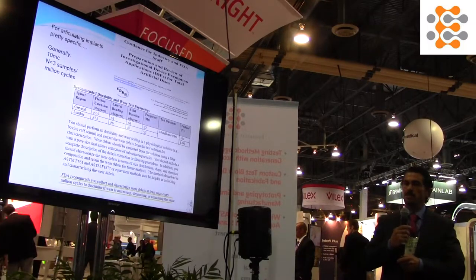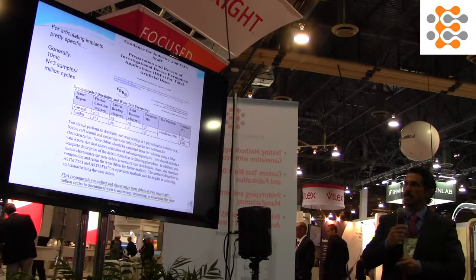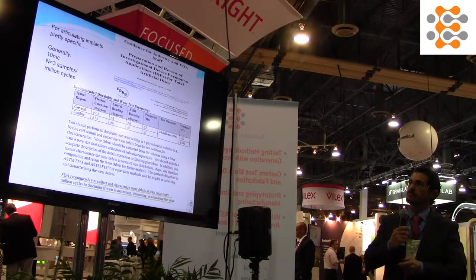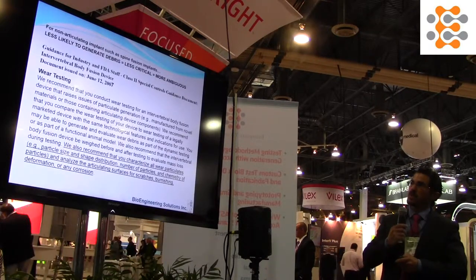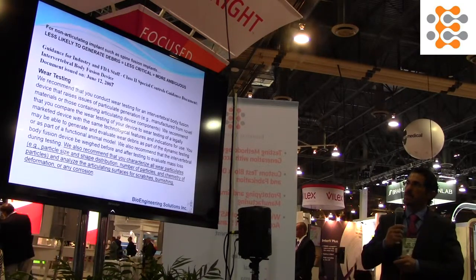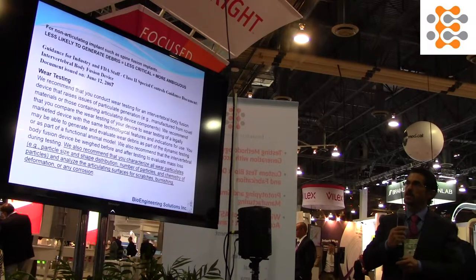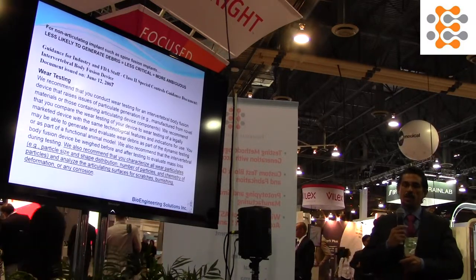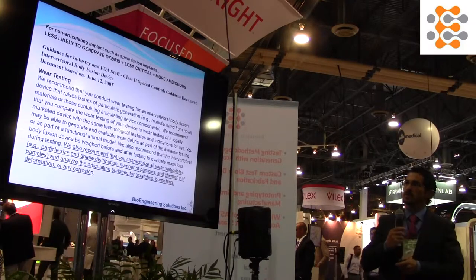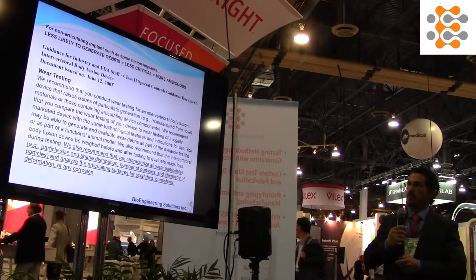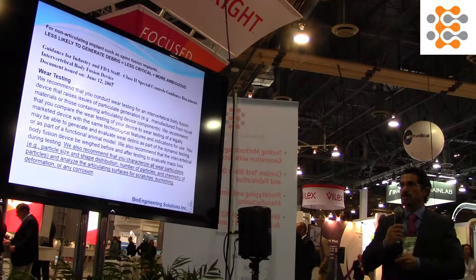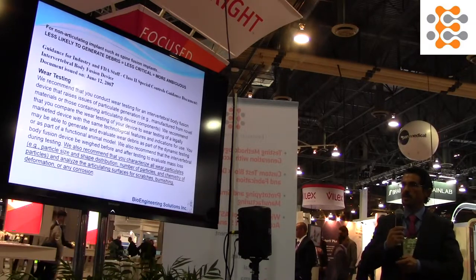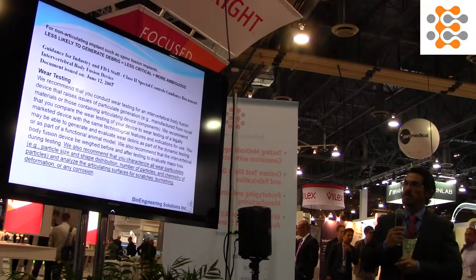If they stay the same, it's enough to convince the FDA, or should be, that things are what they seem. For non-articulating implants that are less likely to generate debris, it's less critical and the procedures are a little more ambiguous. They do still recommend that particle size, shape, and number of particles are characterized, as well as the implant itself.